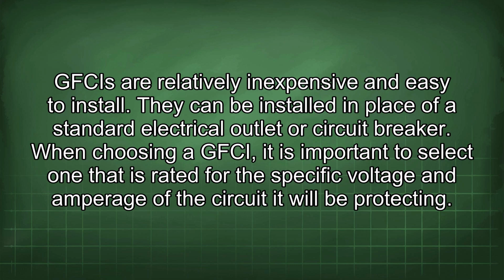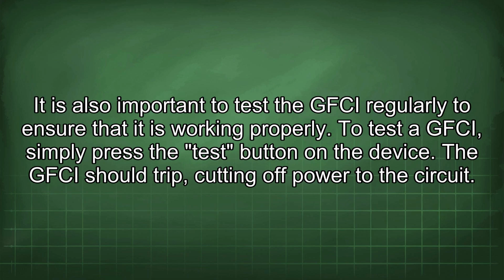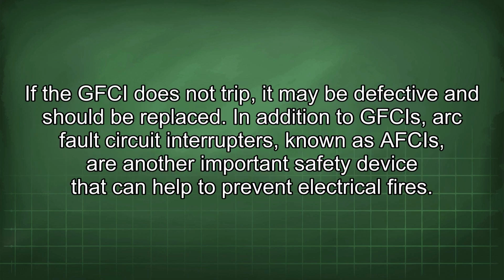When choosing a GFCI, it is important to select one that is rated for the specific voltage and amperage of the circuit it will be protecting. It is also important to test the GFCI regularly to ensure that it is working properly. To test the GFCI, simply press the test button on the device. The GFCI should trip, cutting off power to the circuit. If the GFCI does not trip, it may be defective and should be replaced.